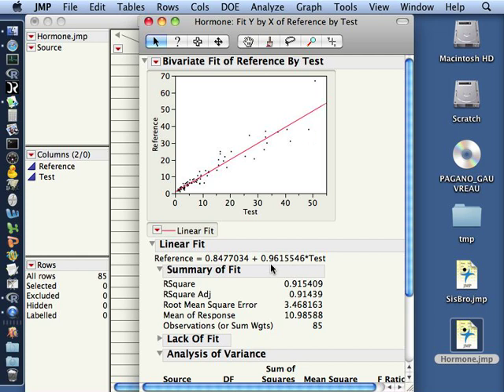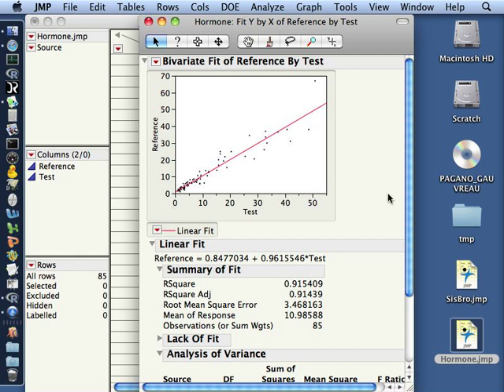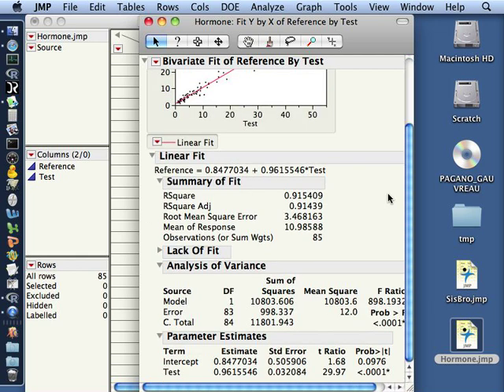And you can see we have a slope that's close to 1. We have an almost perfect prediction from the test to the reference, it's just 0.04 off. If it had been a perfect prediction that would have a slope of 1. The r squared as you can see is 0.915, so almost 92% of the variability in the reference assay is actually explained by the test assay.